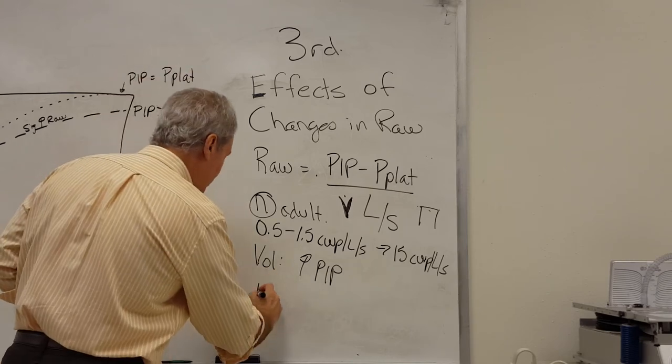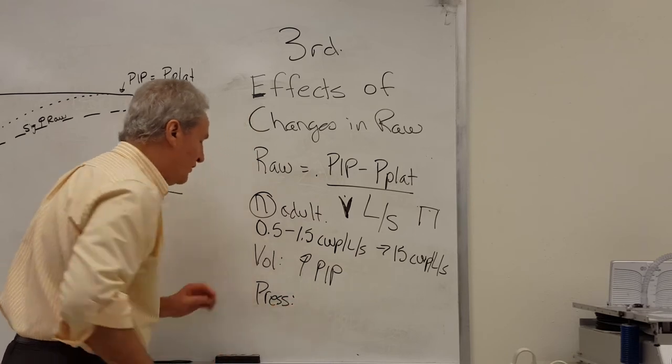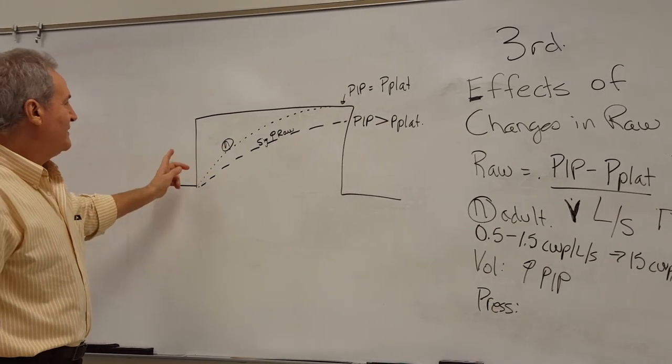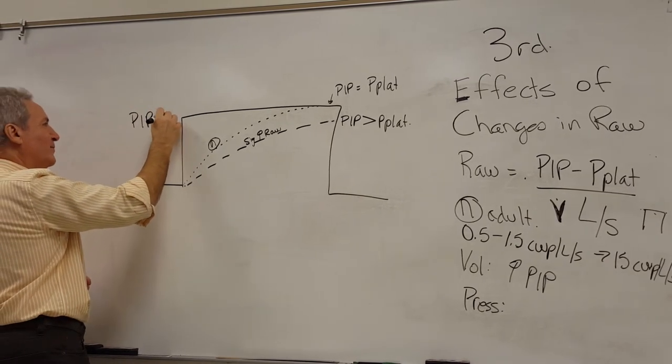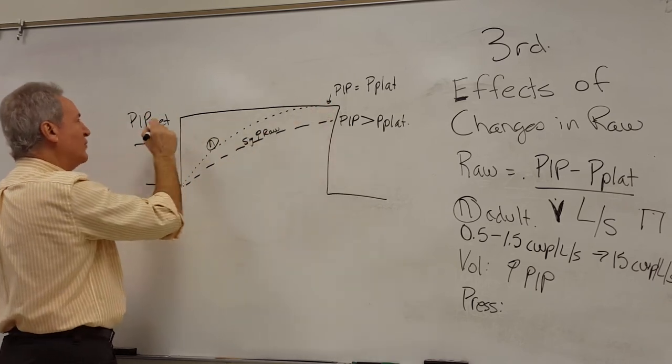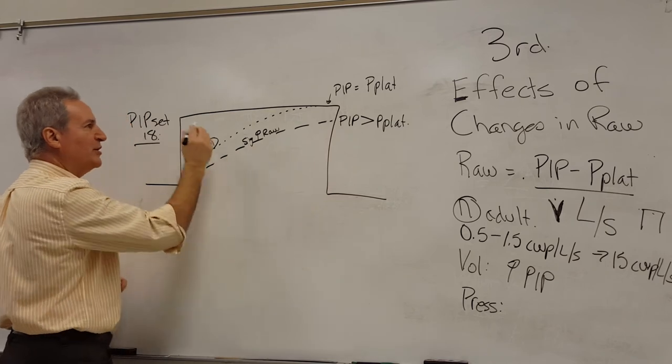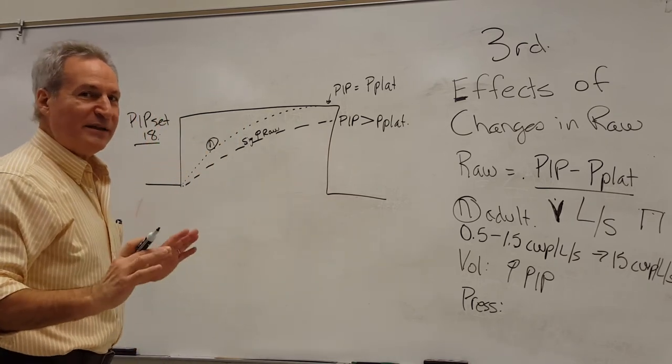What happens if we're in pressure ventilation? Let's move over here for a second. When we look over here, we can see we've got our PIP set at 18. Notice it's a square waveform. We've set our PIP from the beginning of inspiration to the end of inspiration. The pressure is constant.